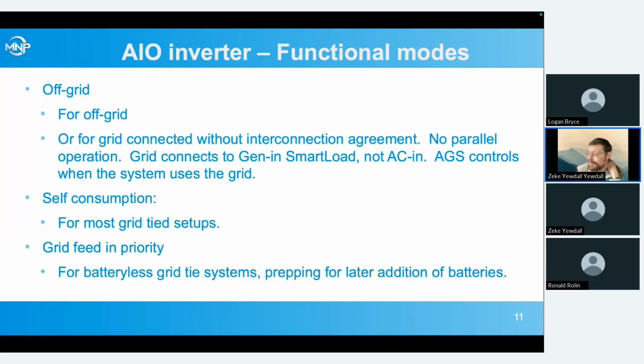This is kind of a big confusion point for grid connected systems, especially. Off grid, that kind of makes sense. We use it for off grid systems. There are also some grid connected systems where you'll want to choose off grid, specifically if you're not getting an interconnection agreement with the utility. You don't want to operate in parallel with them, but you want to operate off your solar most of the time. And you can connect the grid to the generator in and use the AGS controls to control when the system uses the grid. By not operating in parallel with it, it keeps you from having the possibility of accidentally exporting power back to the grid.